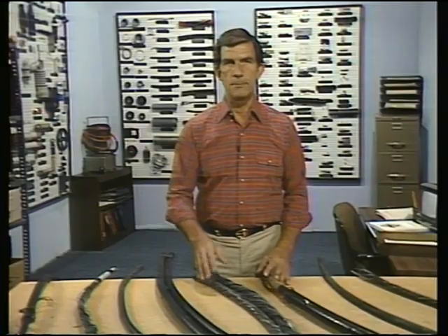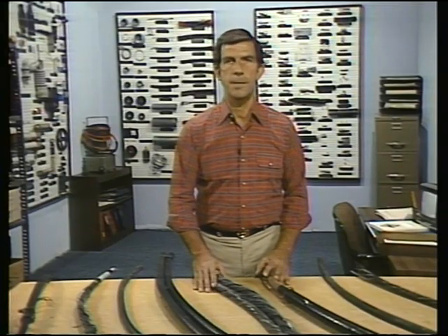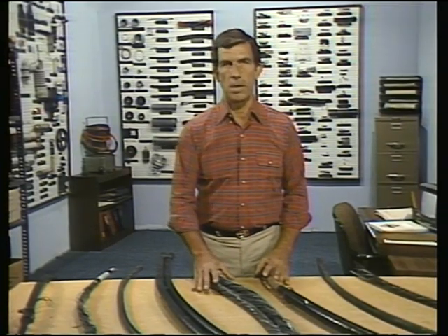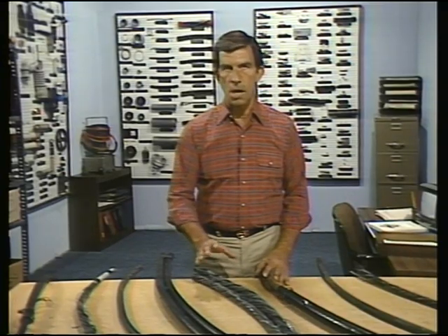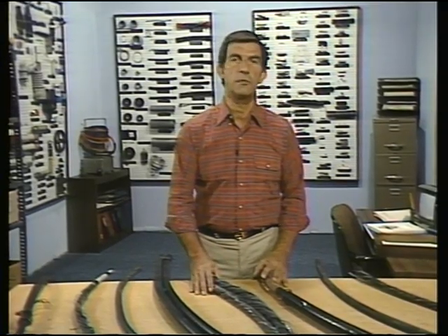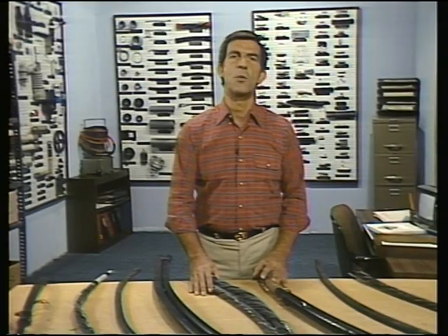In the last part of the program, we saw that a typical URD cable is constructed with a number of different layers. What those different layers are and why they're necessary to keep a cable functioning is what we'll be looking at in this part of the program. Now, you'll recall that the cable we used earlier consisted of a conductor, insulation, and semiconductive layers. The cable is designed to use both a semiconductive and an insulating material to help maintain the integrity of the insulation. There are reasons for this design, and one of these is voltage stress.